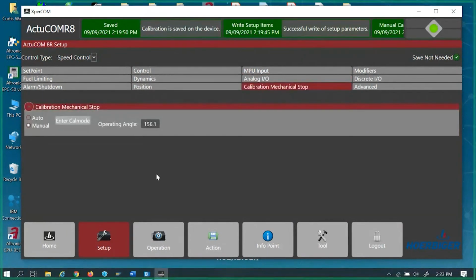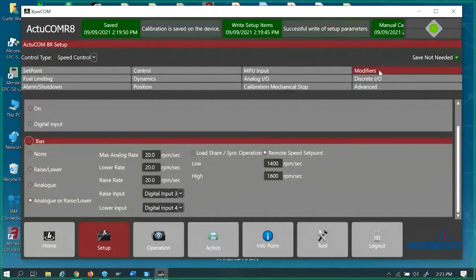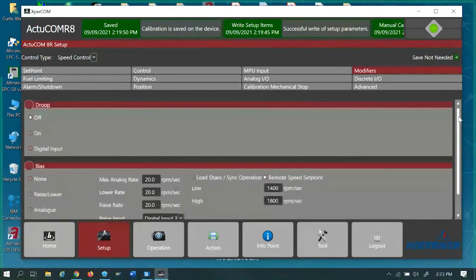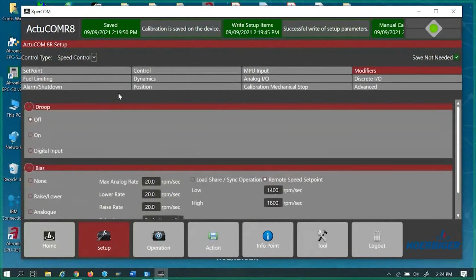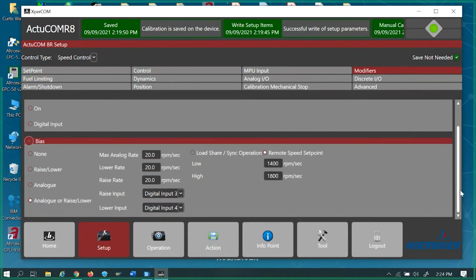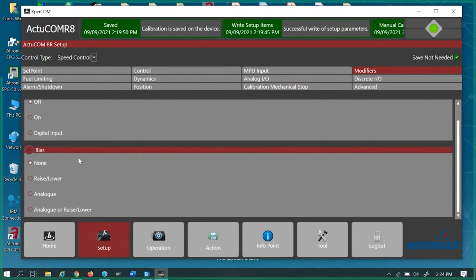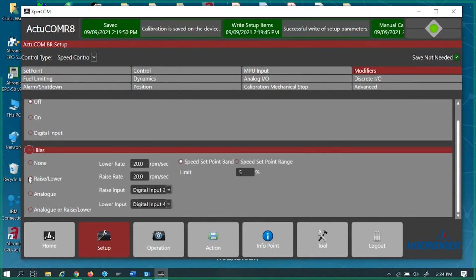We went through the calibration part, modifier parts. A lot of the times this will drive you some crazy. The droop on this, I was told it's not functional. So don't be doing load shares or anything like that for the generator market. Your bias, of course, none is none. You can do a raise and lower. So on your raise and lower switch, if you're just doing a rated deal, we could raise and lower the RPM just by a switch, up or down.